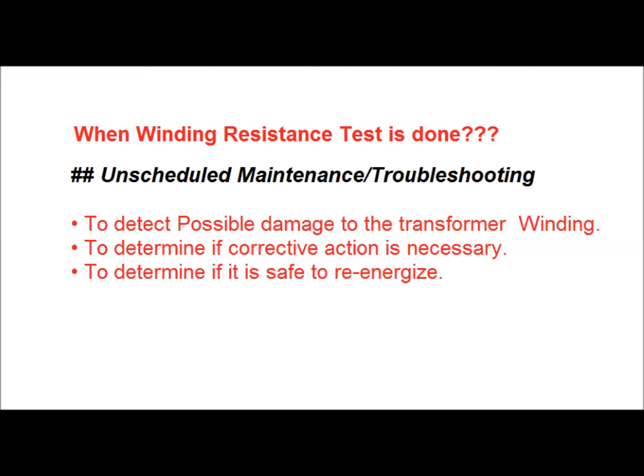Many transformer faults or problems will cause a change in DC resistance measured from the bushing, that is shorted turns, open turns or poor joint or contact. Hence, the information derived from the resistance test is very useful in analyzing the fault or problem.